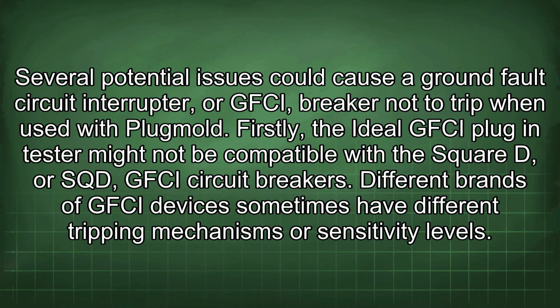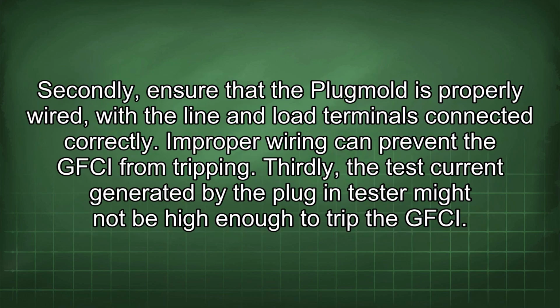Several potential issues could cause a ground fault circuit interrupter, or GFCI, breaker not to trip when used with Plugmold. Firstly, the ideal GFCI plug-in tester might not be compatible with the SQD GFCI circuit breakers. Different brands of GFCI devices sometimes have different tripping mechanisms or sensitivity levels. Secondly, ensure that the Plugmold is properly wired, with the line and load terminals connected correctly. Improper wiring can prevent the GFCI from tripping.